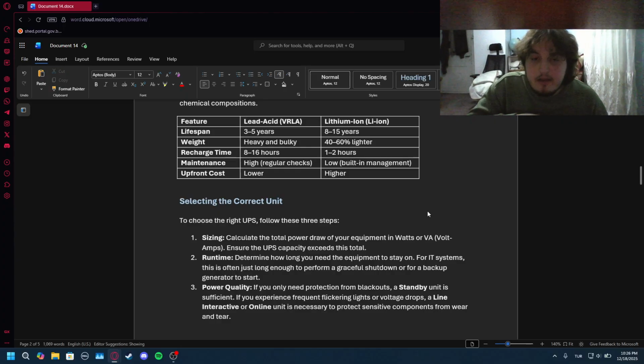Power quality: if you only need protection from blackouts, a standby unit is sufficient. If you experience frequent flickering lights or voltage drops, a line interactive or online unit is necessary to protect sensitive components from wear and tear. You can just basically use a simple UPS and you'll be fine.